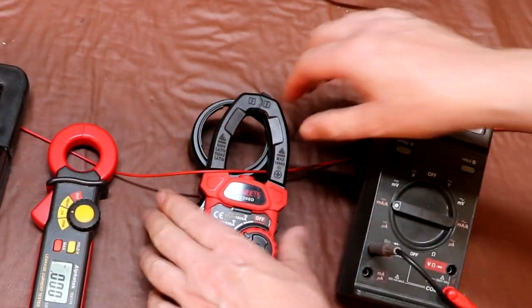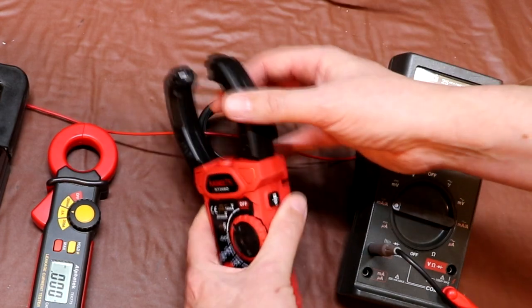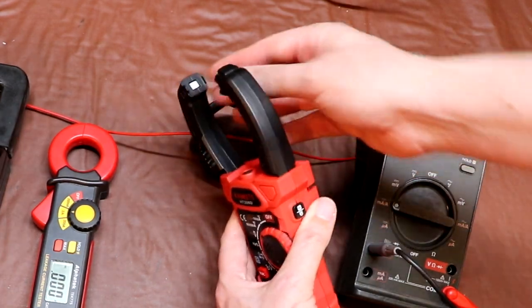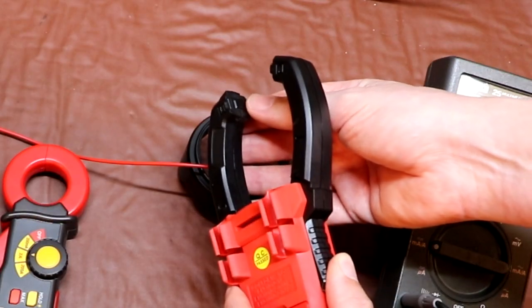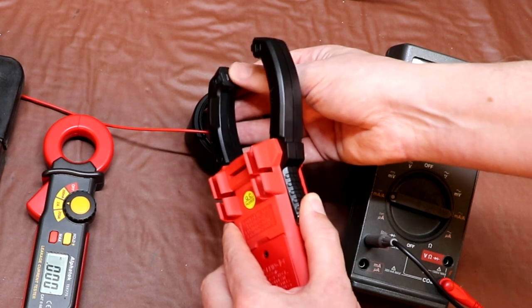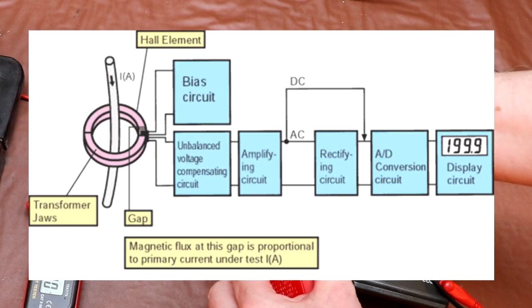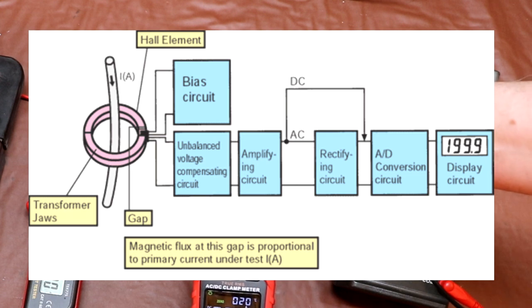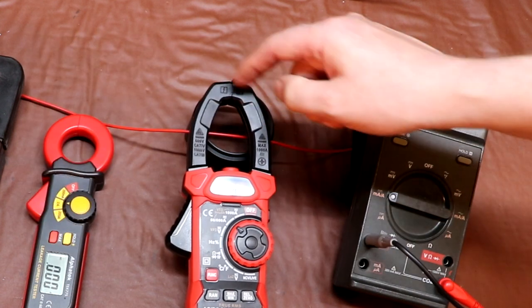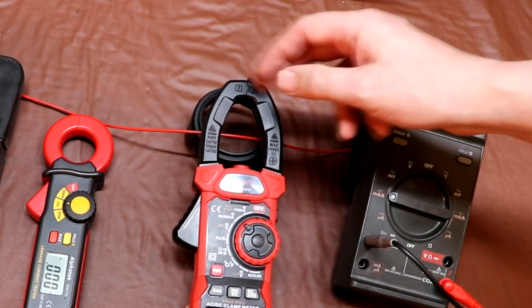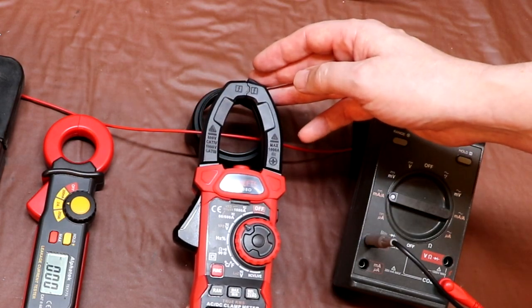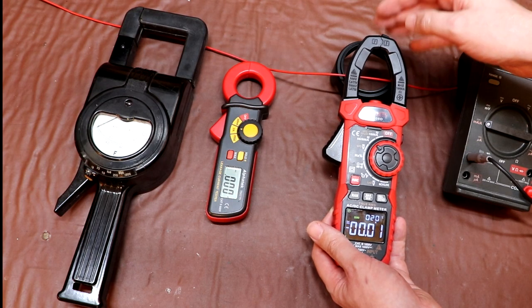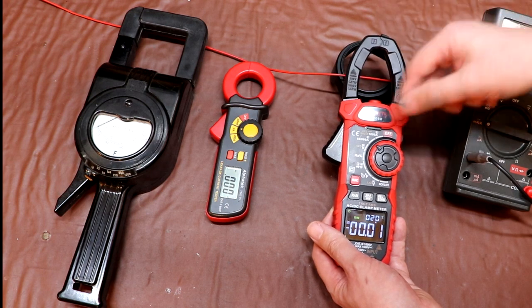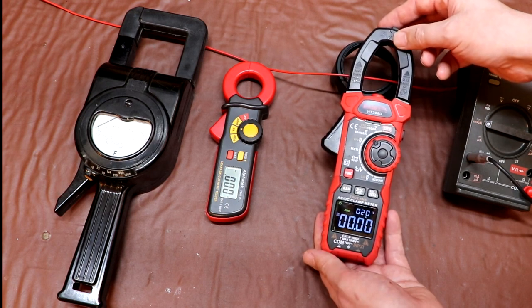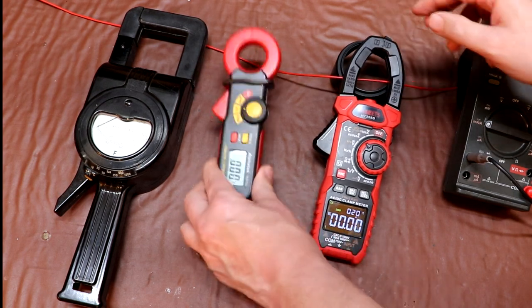But if we disconnect our KAIWEETS meter from circuit, and again hopefully you can see the jaws there, there's a piece of metal there, but on the opposite jaw there's no metal, just a piece of plastic. What's behind this piece of plastic is a Hall effect transistor. So rather than acting like a transformer, this meter is directly measuring the magnitude of the magnetic field flowing around here. It's taking a direct measurement of that magnetic flux, or probably better to call it a Gauss. Because this meter is based on a Hall effect transistor which directly measures the magnetic field rather than relying on a transformer, the KAIWEETS meter is able to measure DC when our other two meters can't.